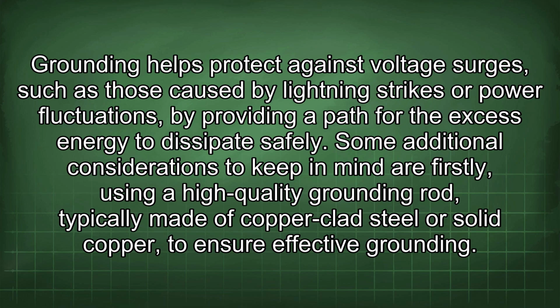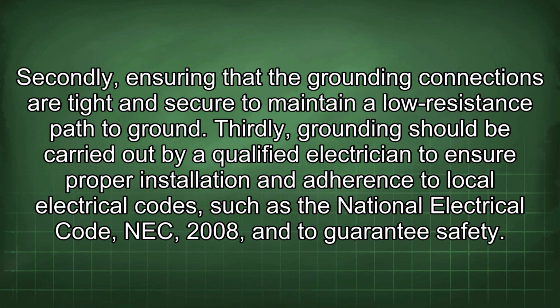Some additional considerations to keep in mind are: firstly, using a high-quality grounding rod, typically made of copper-clad steel or solid copper, to ensure effective grounding. Secondly, ensuring that the grounding connections are tight and secure to maintain a low resistance path to ground. Thirdly, grounding should be carried out by a qualified electrician to ensure proper installation and adherence to local electrical codes such as the National Electrical Code, NEC, 2008, and to guarantee safety.